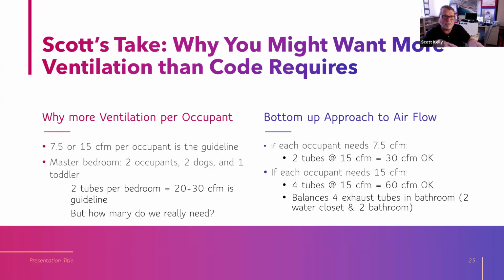We've already gotten past the argument over 7.5 CFM or 15. We're settling on the 15, but we've got the toddler and the 2 dogs, so actually we need 4 tubes into the master bedroom. When I say 4 tubes into the master bedroom, you can kind of see in the background over here, there's a boot, and those 2 tubes go into the boot, so you have these 2 boots that would be bringing in this air, right? So it's bringing in 4 tubes of air into the master bedroom, which theoretically would be 60 CFM, and the master bedroom door is closed, and then there's a bathroom, of course, in the master bedroom because it's en suite.